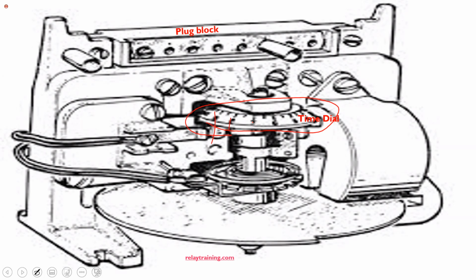Below your time dial, it would really help if we had the physical thing, but right here, that's your movable contact. And here, that's your counterbalance spring. The movable contact is on top of that spring, and all of that is connected to your disc. So as the disc rotates, it will move the contact. Now, once the input is removed, the contact will return to its rest position.